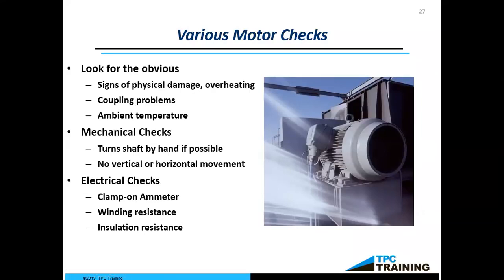The ambient temperature got too high. The mechanical checks I mentioned before, we want to make sure the shaft will turn and no vertical or horizontal movement. That tells me something about the bearings. And then the electrical checks, remember the clamp-on ammeter when the motor is running is a great diagnostic tool. And when the motor is not running, we definitely can check the windings with a regular ohm meter, and we can check the insulation with a megger.